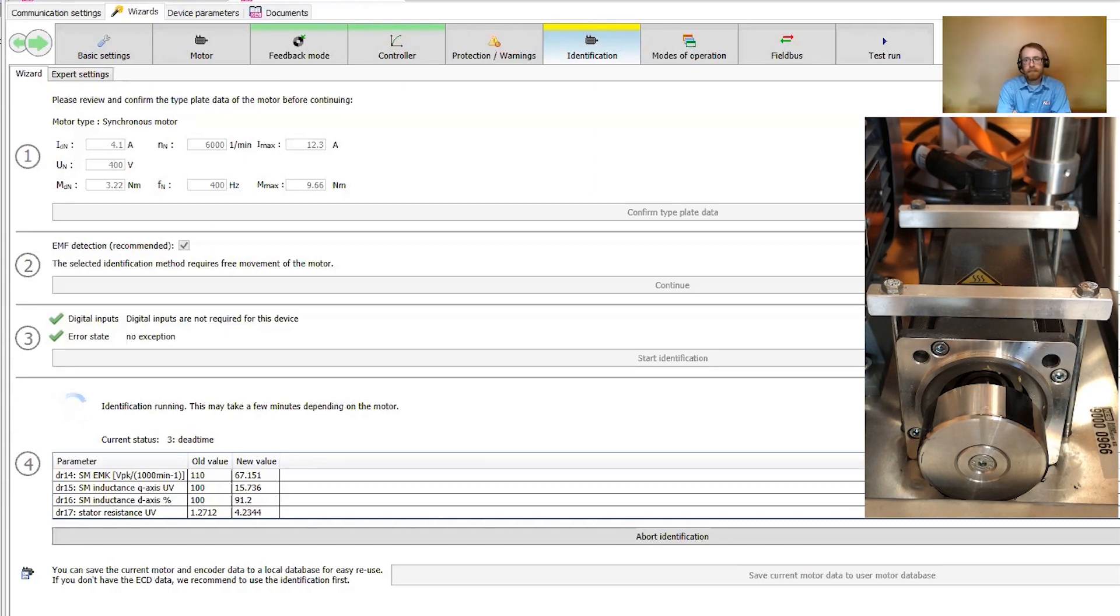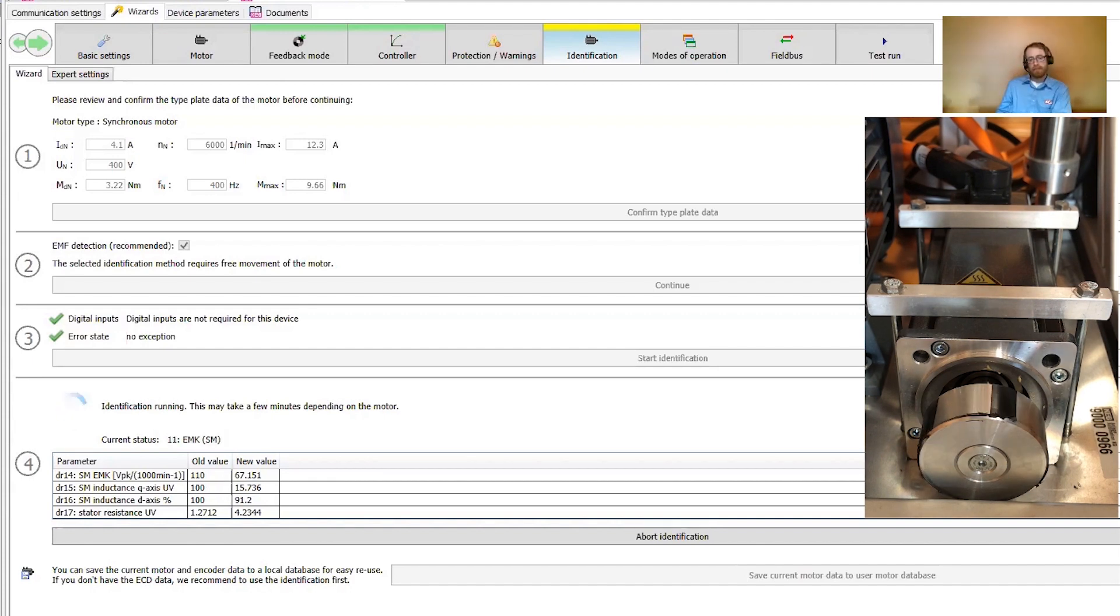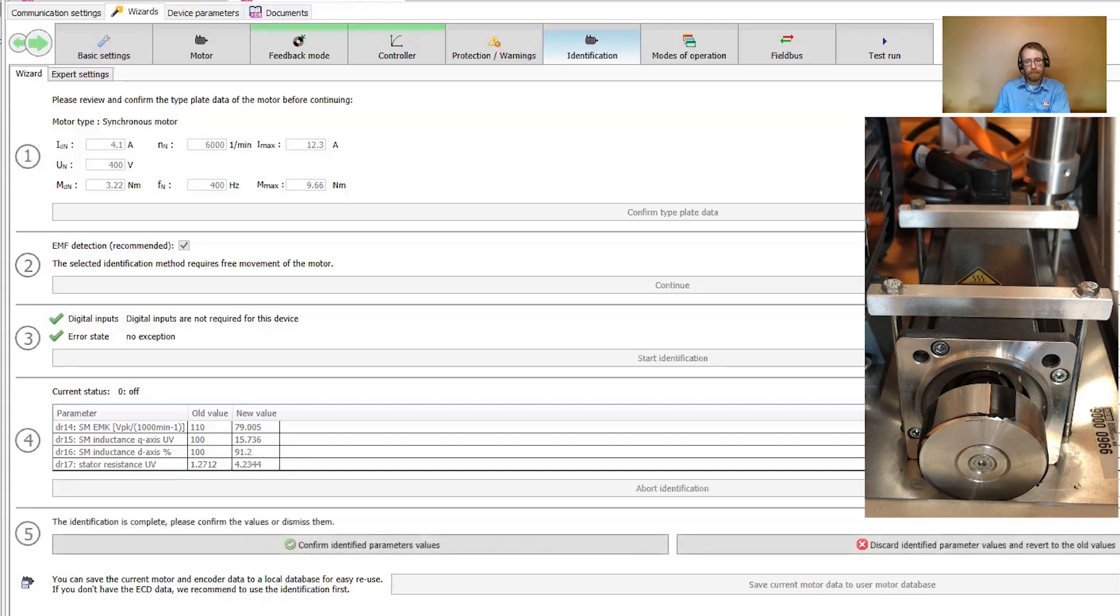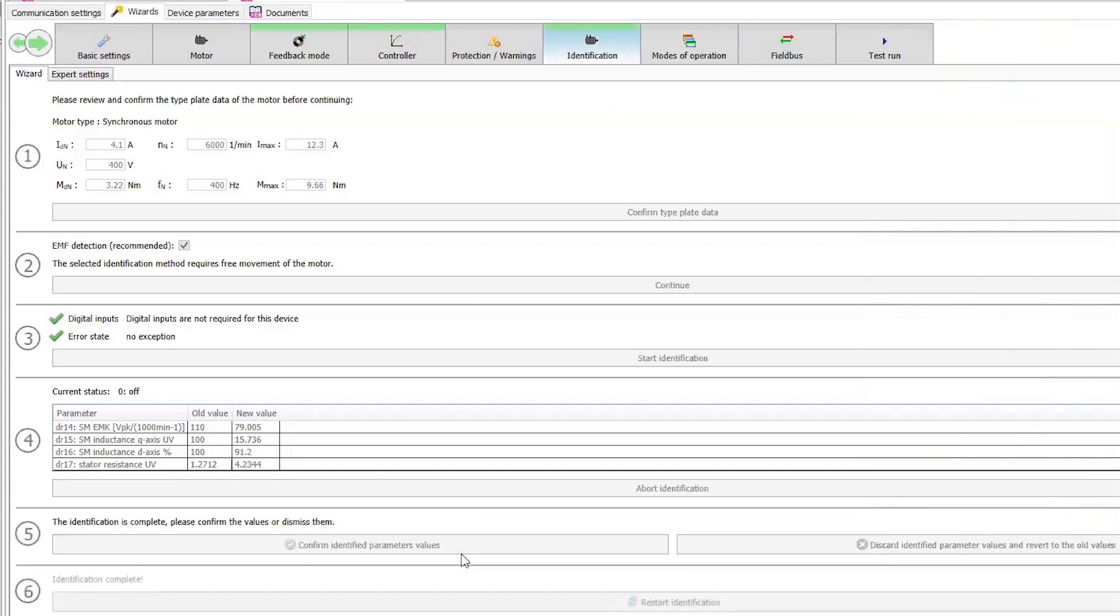During the process, the inverter will learn the motor resistances and inductances. Then towards the end, it will ramp up to speed to measure other characteristics. When the process is complete, I'll click to confirm and save the data and turn off the hardware enable.